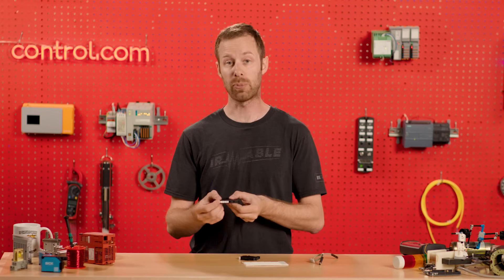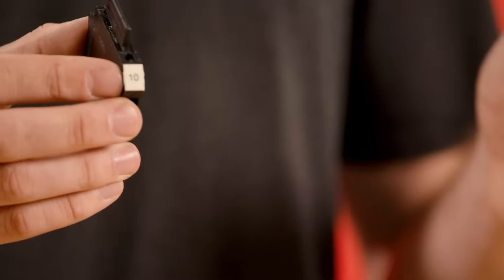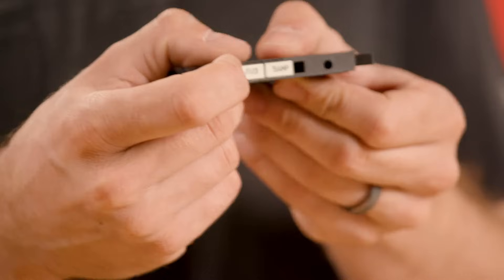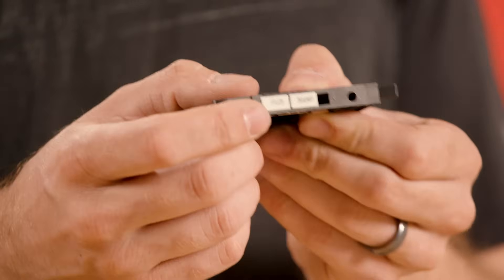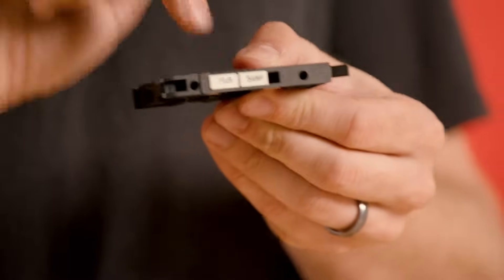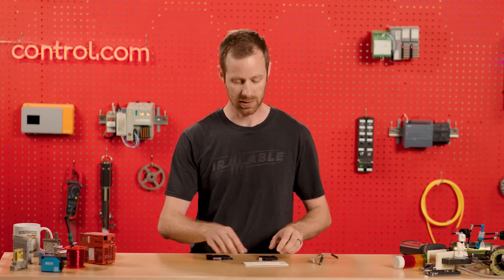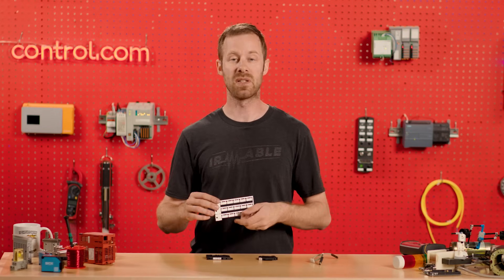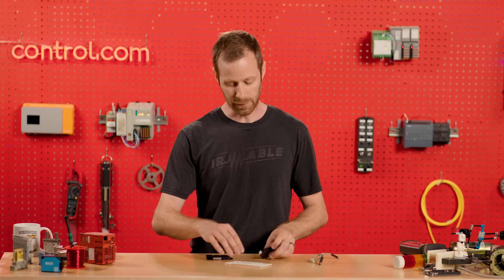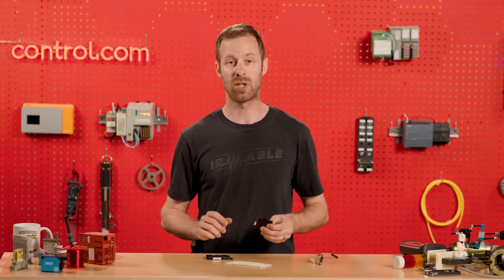Either way, labels can be attached properly so they can be read and evaluated very quickly. Sometimes you can get pre-printed ones — for instance, an entire row of blocks numerically ordered, or labeled as FU3, the third fuse in a setup. For custom labels, you can custom print with ink onto the label and attach it to the front of the terminal block. These come in all shapes and sizes, and every manufacturer of terminal blocks supplies the right labels for labeling on the fronts, sides, or even at the top and bottom.